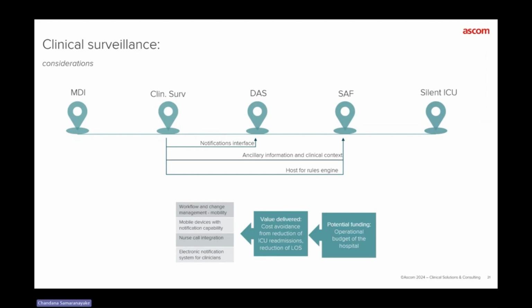When you build a system like that, you need to ensure it can host the kind of algorithms needed for a future smart alarm filtering system that can reduce the alarms going to the caregiver's mobile device. That's one major component. It needs a notification interface that can spread notifications about deterioration happening to the patient, which are not alarms but results of calculations performed on the incoming data. It also needs to create a digital twin of the patient and provide guidance to a future smart alarm filtering system on the patient's situation.